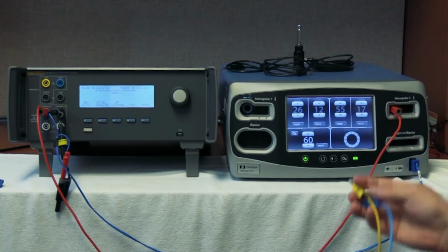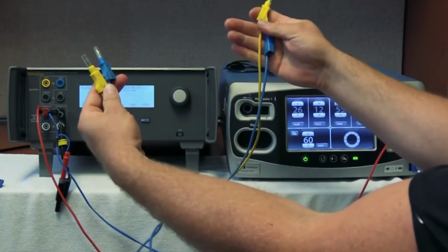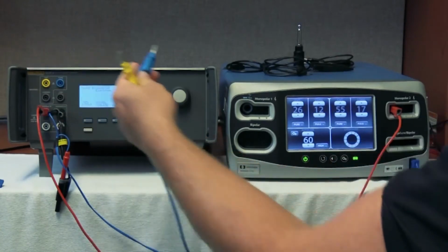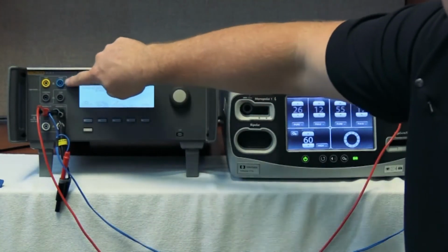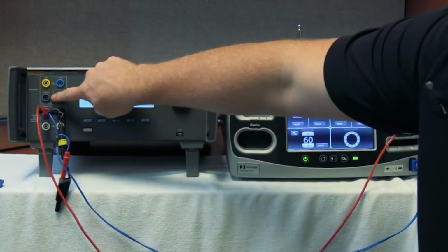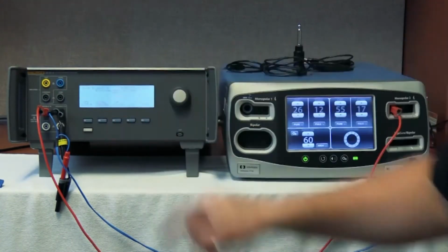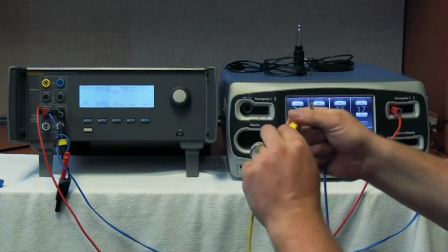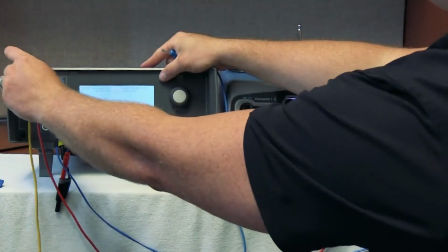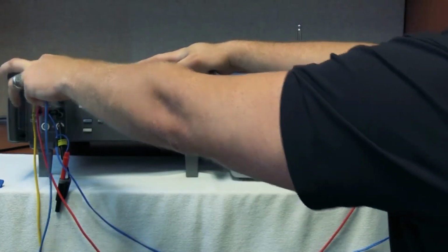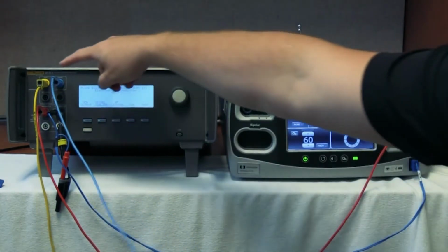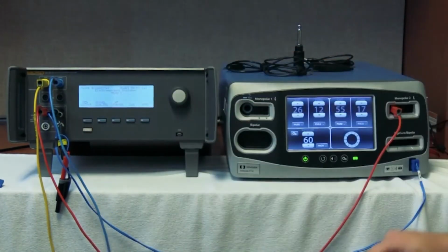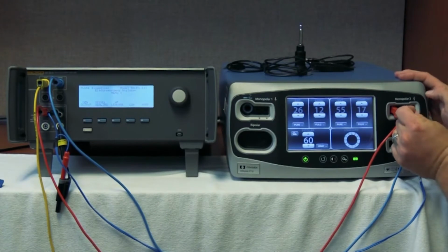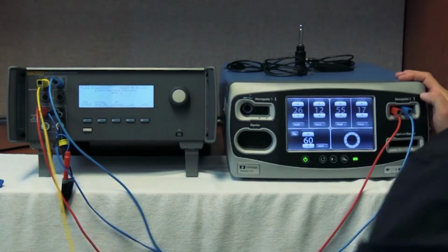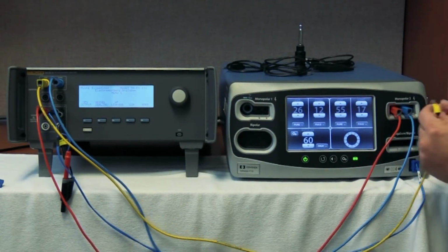We're going to simulate a foot pedal using the yellow and blue cables from the QA-ES III. This top quadrant is to simulate the foot switches of the ESU. We'll connect the yellow cable to yellow and the blue cable to blue. On the FT10, they're inverted, so where yellow's on the left and blue's on the right, we're going to put blue on the left and yellow on the right.